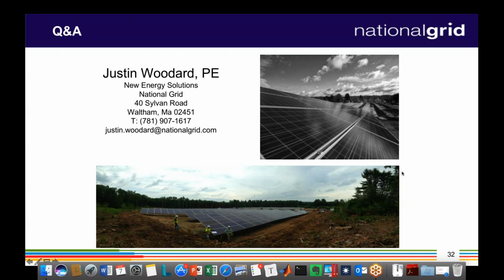We're approaching 100% in some cases of nameplate loading capacity in reverse power flow, and it's only on certain days. There's a certain area of our system in a load zone that's beneficial, where land is inexpensive relative to other areas, so we've seen a huge amount of PV penetration there. A few substations in that area, one normally backfeeds almost any given day - probably right now it's backfeeding. Other areas, under the right conditions when loading is light, like a Saturday or Sunday when manufacturing or industrial load is light, we'll see lots of generation on the feeder, and we're starting to approach 100% of rating in backfeed.